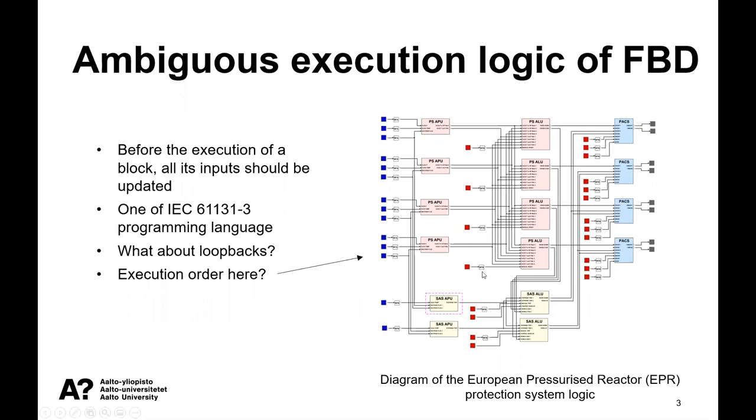This can be implemented differently in different standards. For example, in IEC 61131-3 standard, the function block diagrams are executed from top to bottom and from left to right. Well, first from left to right, and then from top to bottom. And you might remember it from CodeSys, how those networks are executed.